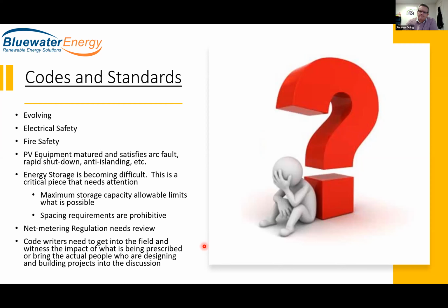Spacing requirements are becoming prohibitive. If we need a meter of spacing between energy storage units, then we go from needing a couple feet of wall space to needing 15 to 20 feet of wall space. So it becomes prohibitive in that regard.